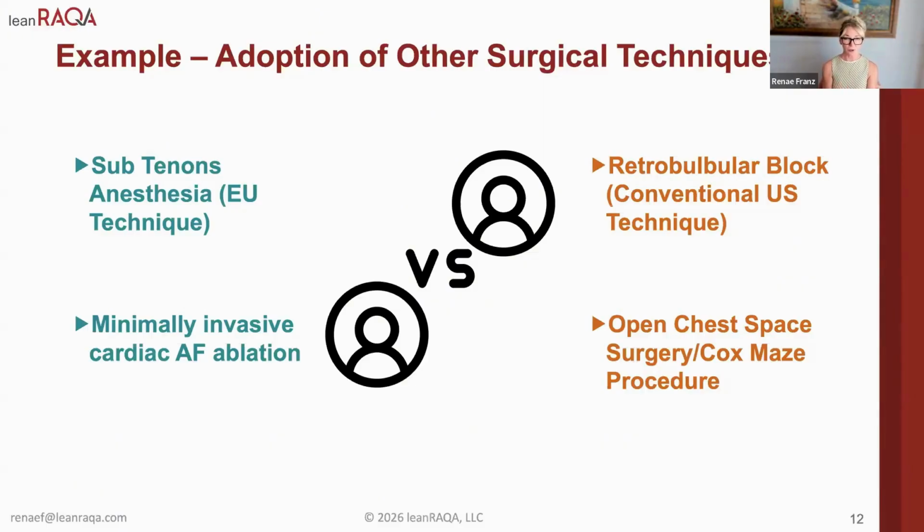This company had a device, it was brilliant, and it worked well, that could actually remotely enter the exterior of the chest. It went up through the xiphoid process into the pericardium, and you could remotely control it and make the same burn patterns with radio frequency energy remotely that you could do as a surgeon with the chest cracked open. The problem was the surgeons were not trained in that remote technique. And though the product worked well and they raised $70 million, it did not make it into the market in its intended format because the end user could not use it.